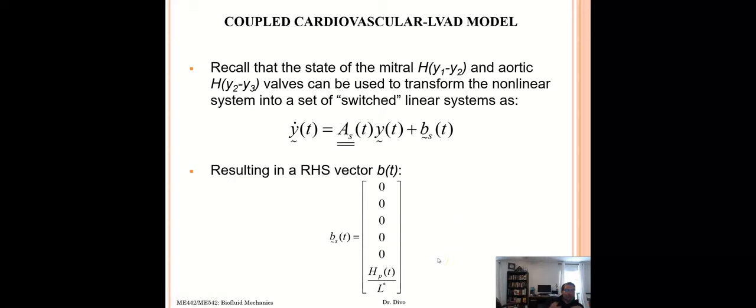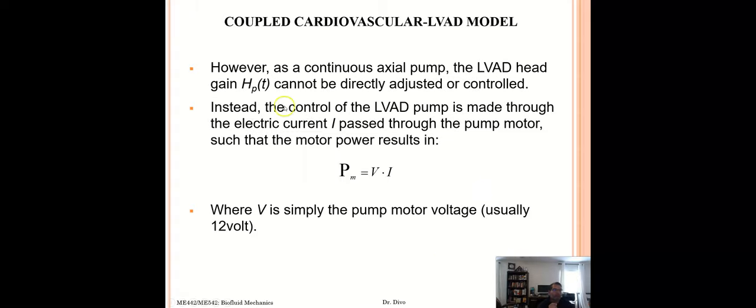But as I mentioned, even though this is a continuous flow axial pump, it doesn't act as such, because the flow that it receives, or the supply of blood in the inflow cannula, changes as a function of the heart rhythm itself. So the pump actually acts as a pulsatile pump, even though it's not mechanically designed to be so. So as a continuous axial flow pump, the LVAD head gain cannot be directly adjusted or controlled.